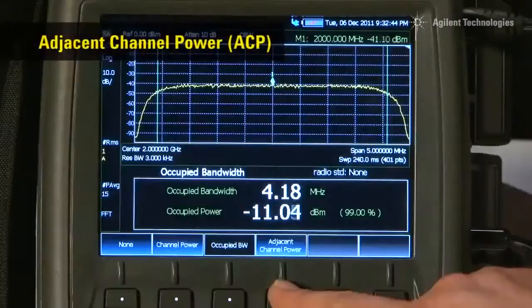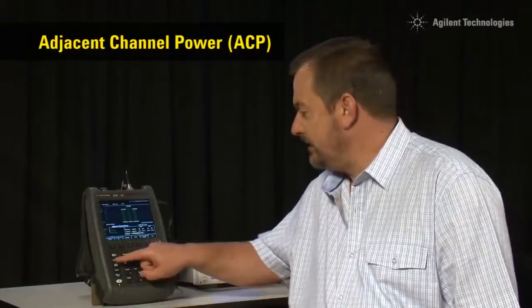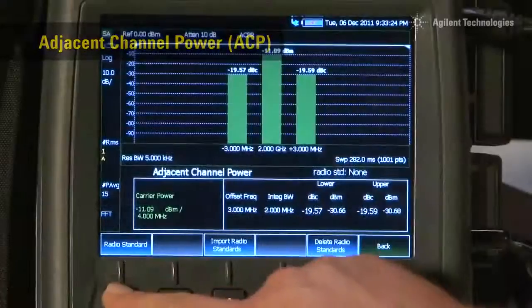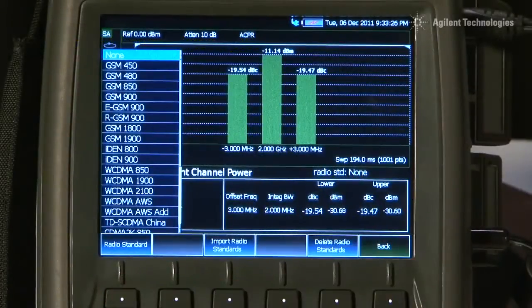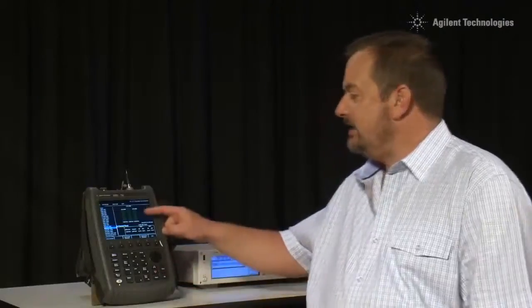We can even measure the adjacent channel power, and if we are working to a radio standard such as, in this case, WCDMA, we can recall that standard and the adjacent channel power measurement will automatically configure itself to measure adjacent channel power properly for that radio standard.